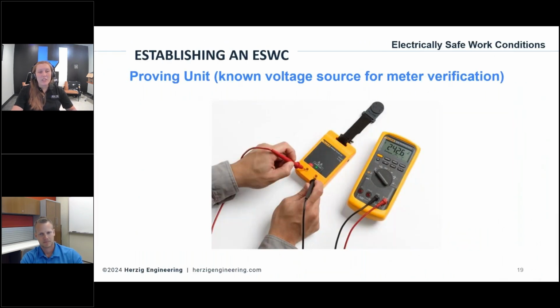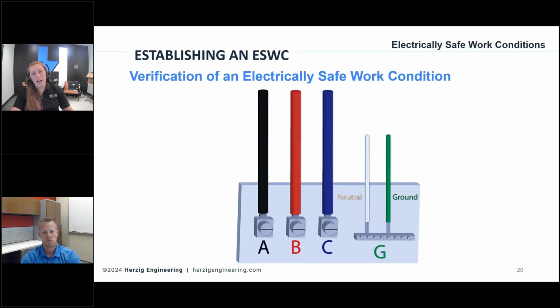And if you don't have a good known voltage source in your area, there are proving units. They make them. You don't have to get this. It's definitely not required, but they are super handy to carry around, especially if you have to do this quite often. By hand, mind you. This is the by hand method. Okay. So it's got AC or DC on this proving unit, and then you just put the leads in, super low current. There's no hazard for you here. You're just getting that voltage check, 240, 242 volts, whatever. You've got your known source. And when you're doing that phase to phase and phase to ground, like I said, do it all. A to B, A to C, B to C, A to ground, B to ground, C to ground, and if you're at a service entrance, neutral to ground as well.